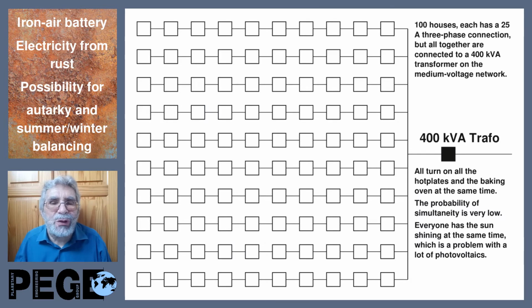Grid connection of a typical small village of 100 small houses. Each house has a 25 ampere 3-phase connection to the grid. This is 17 kilowatt, but all the 100 houses are only connected by a 400 kilovolt-ampere trafo station. And 400 divided by 100 is only 4. How can this work, that they promise everybody you have 17 kilowatt, but in reality it's only 4 kilowatt, and everybody at the same time?